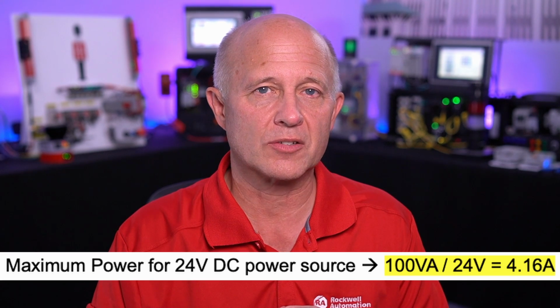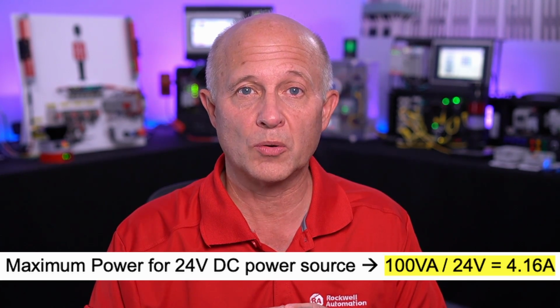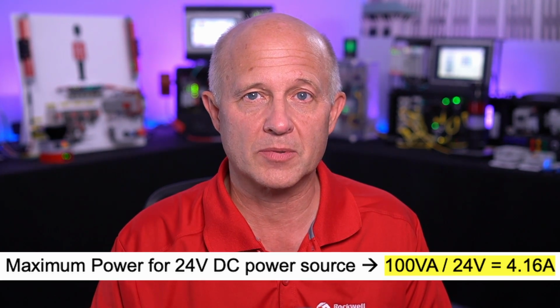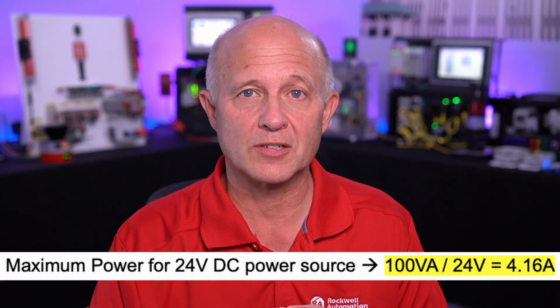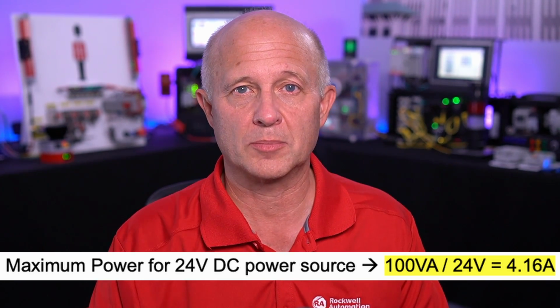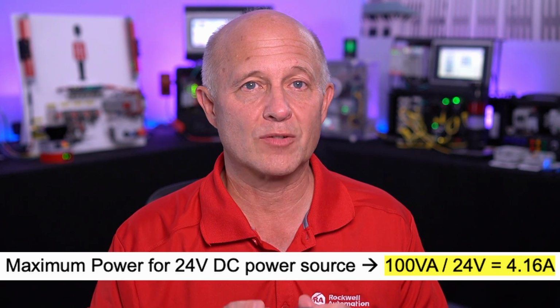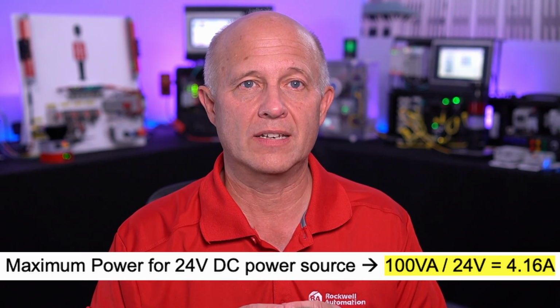Now let's discuss one very important topic that's commonly overlooked or at least misunderstood, and that is Class 2 power supplies. National Electric Code Article 725 sets the requirements for the elimination of fire hazards in 24 volt DC circuits. It states that the maximum power potential for these circuits be limited to 100 volt amps or 4.16 amps. Many of your field devices that are supplied by that 24 volt power supply are labeled such and required to be fed from a Class 2 rated device.